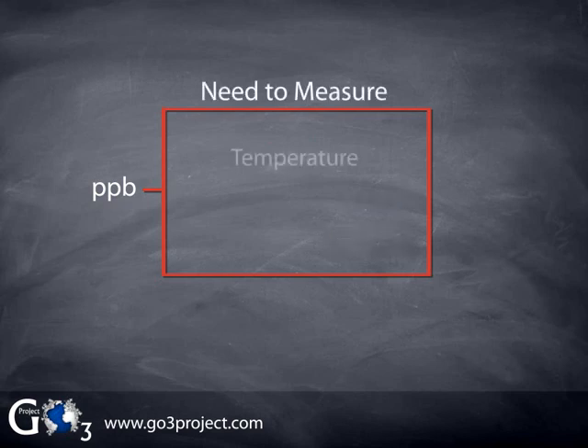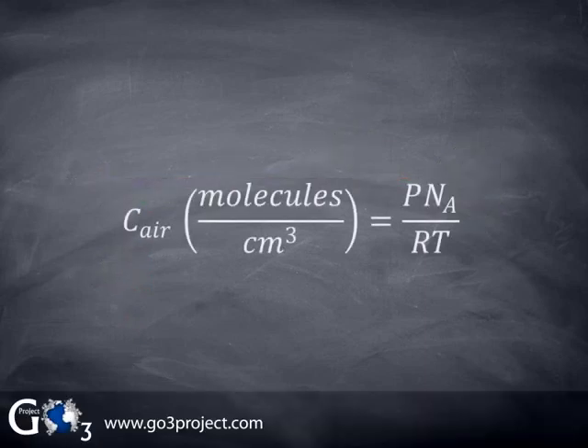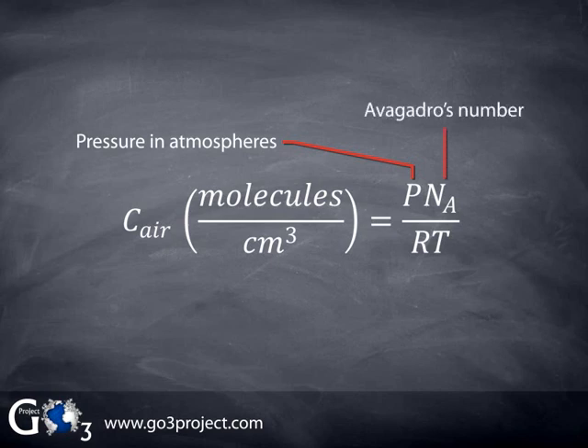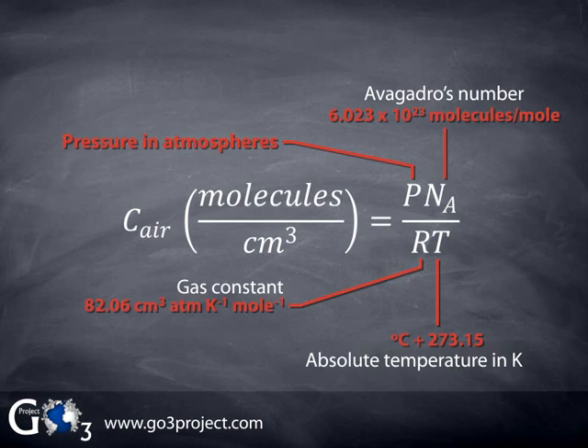The concentration of air molecules is completely determined by the temperature and pressure. So, to convert our ozone measurement from concentration units of molecules per centimeter cubed to mixing ratio in PPB, we need to measure the temperature and pressure inside the detection cell. This is done by adding temperature and pressure sensors to the ozone monitor. We can calculate the concentration of air molecules inside the detection cell using the ideal gas law. Here, P is the pressure in atmospheres, N sub A is Avogadro's number, R is the gas constant, and T is the absolute temperature in Kelvin. Avogadro's number and the gas constant are accurately known constants. We only need to measure P in atmospheres and T in Kelvin to calculate the concentration of air molecules. If we measure T in Celsius, we can convert it to Kelvin by adding 273.15.